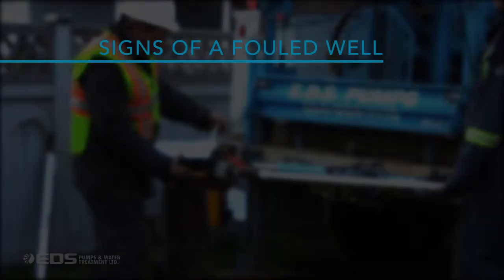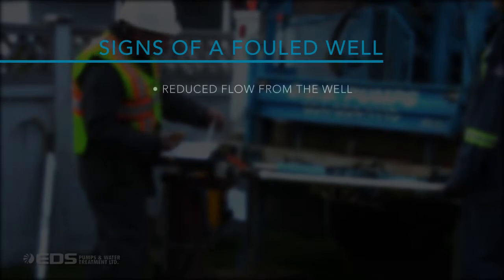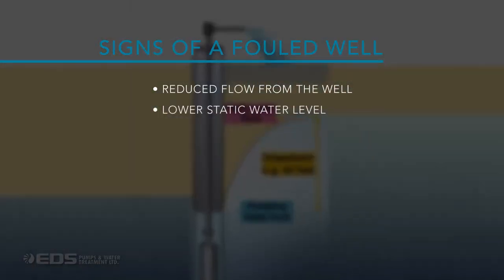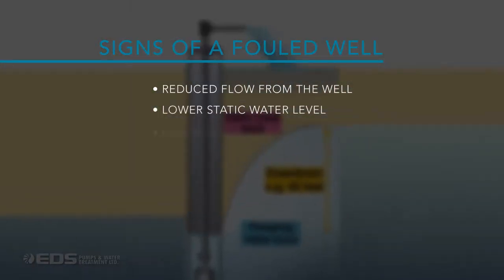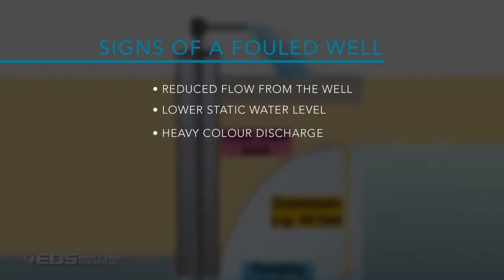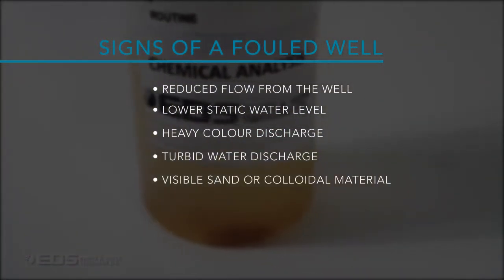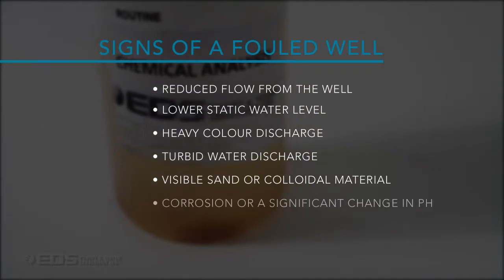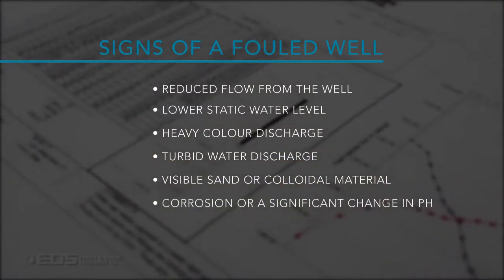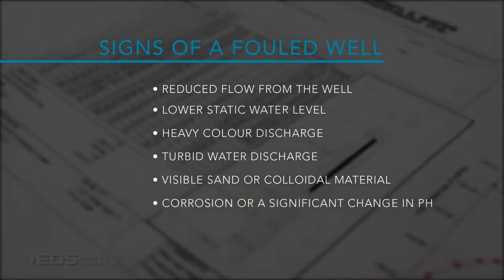Signs that a well is beginning to foul include reduced flow from the well, lowered static water level, heavy color discharge, turbid water discharge, visible sand or colloidal material, and corrosion or a significant change in the pH.